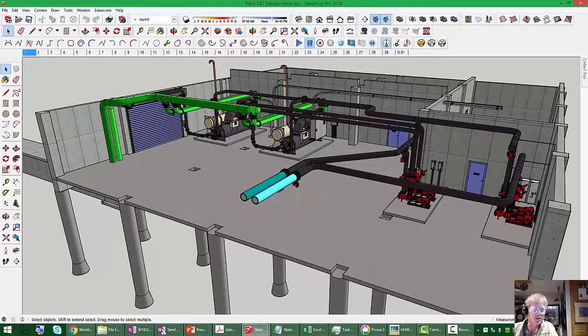And it's not out of the question that you'll go into a plant that's supposed to be variable flow, it's configured as variable flow, but it actually isn't running that way because for whatever reason there's three-way valves out in the system, a lot of three-way valves. I've seen it before, and so that'd be an opportunity. So the answer to the first question is that it's a variable flow primary secondary plant.